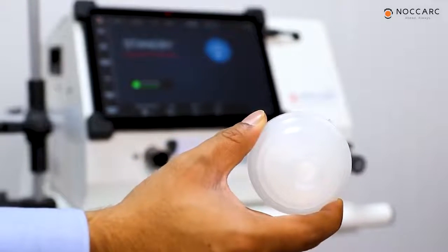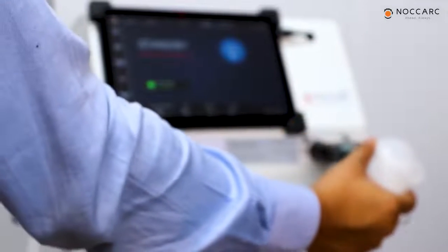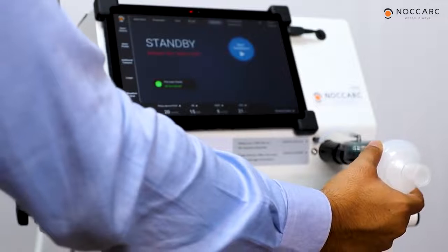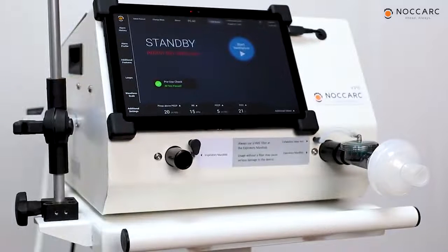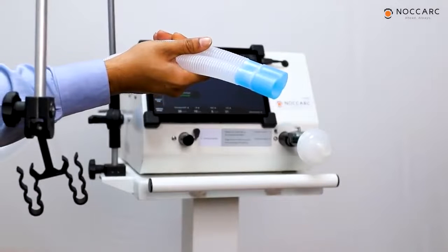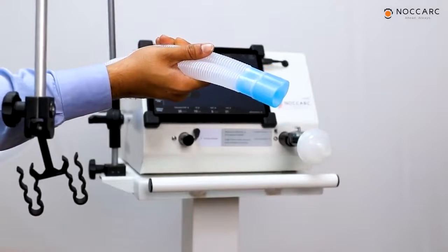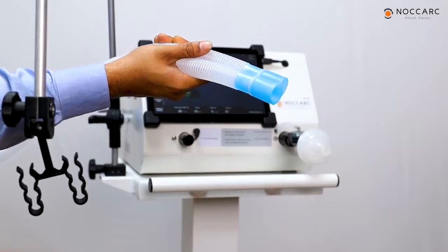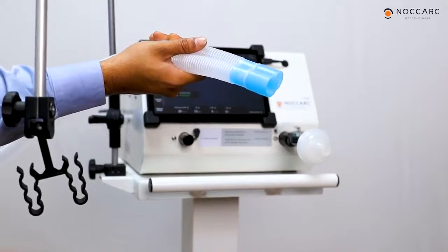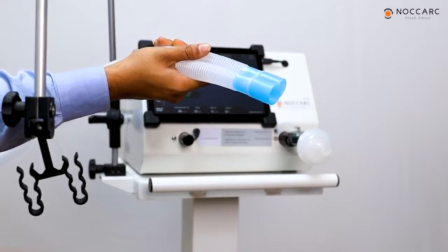Connect one HME filter at inlet of active exhalation valve. This filter will help to avoid secretion coming from patient side. It will help to increase the life of active exhalation valve. Connect patient circuit to inspiratory and expiratory port as per patient type. Currently I am using adult patient circuit.